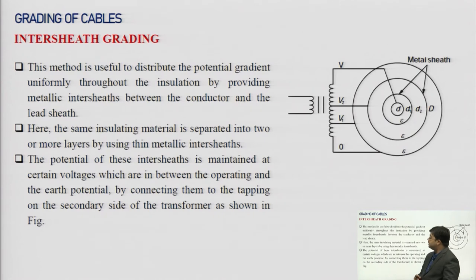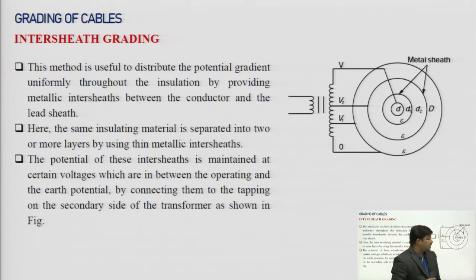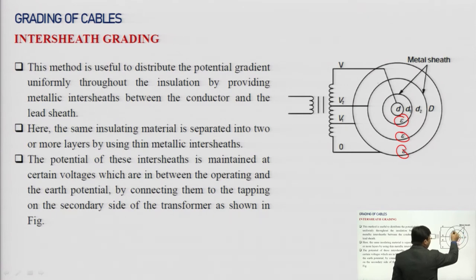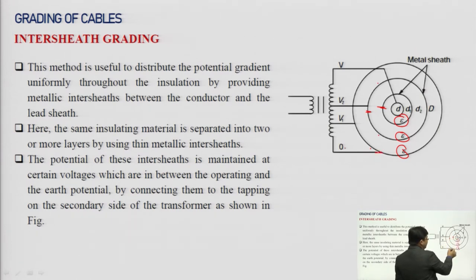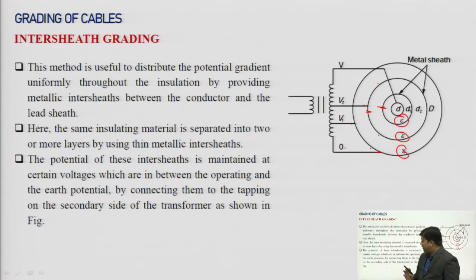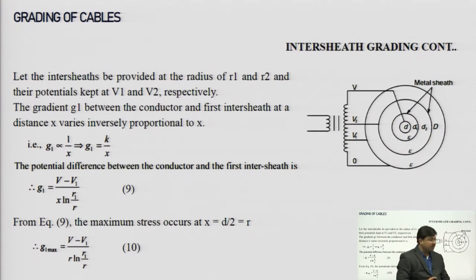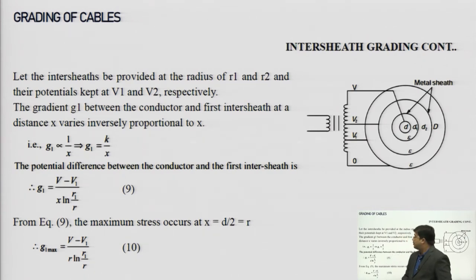Inter-sheath grading is useful for distributing the potential gradient uniformly throughout the cable. Here the dielectric material is common (same permittivity ε), but metallic inter-sheaths are provided inside the cable. Two inner metal sheaths are provided, creating voltage levels 0 at the outer sheath, then v₁, v₂, and total voltage V at the conductor. The inter-sheaths maintain a uniform voltage gradient. The problem is to find the correct placement (radius) and voltage of each inter-sheath.